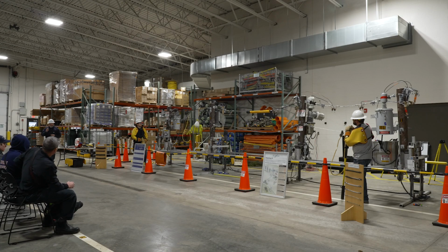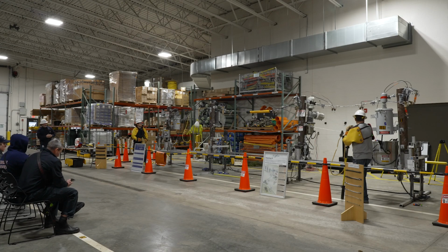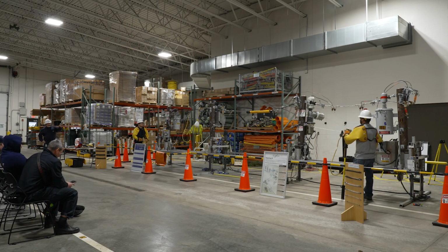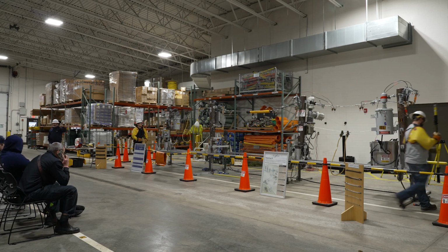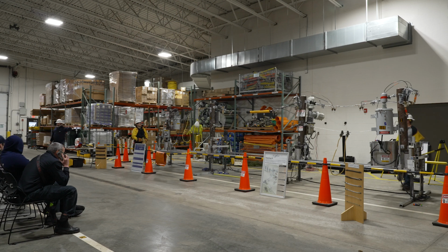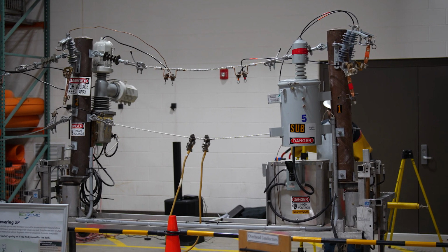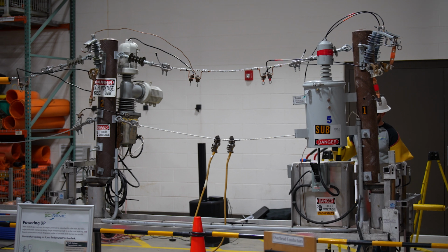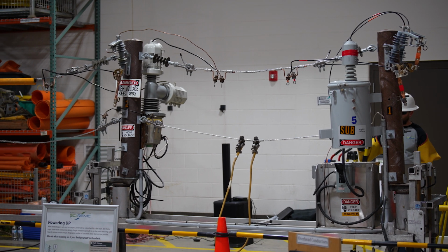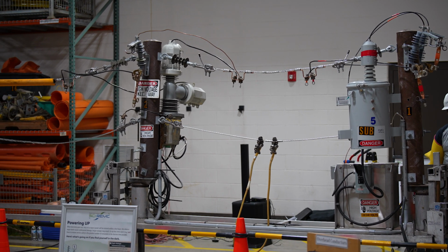Now we're going to show you what a three-phase device is on our downlines. This is an electric circuit recloser, and it's not going to make any noise. That was a one-shot; this will go four shots to lockout. 1, 2, 3, long burn.